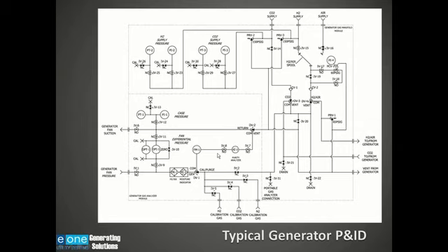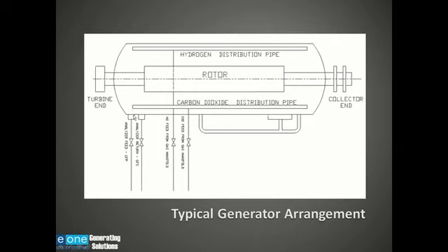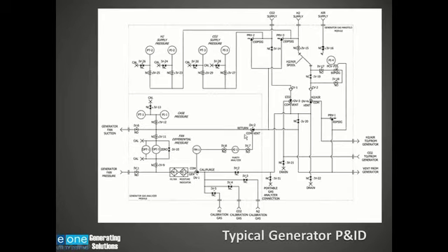When I'm purging the generator, I don't want to take a sample here, because if I've got CO2 in the generator, that's all it's going to see is CO2. I need to get a representative sample of what's leaving that generator. So what I do is I tie my analyzer to the vent where the gas is exiting and going to atmosphere. And now that gas coming out, going through my analyzer, that's where now I've got a representative sample of the gas that's coming out of that generator during the purging process.